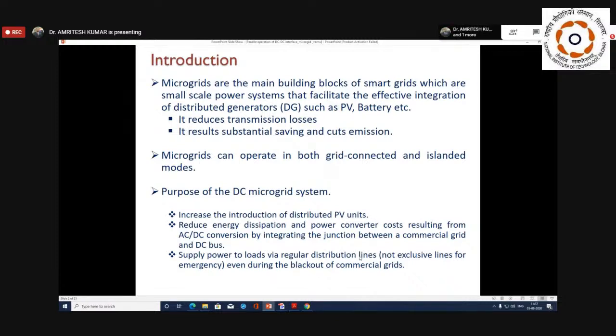Microgrids can be operated in grid connected mode and islanded mode, depending on the location. It might be connected with the grid, and it may operate in islanded mode also, and sometimes we say off grid mode. Islanded and off grid are two different things. Islanded means there is a possibility of being connected with the grid, but off grid means that the system is completely isolated from the grid and is operated in a sustained manner without the help of any grid.